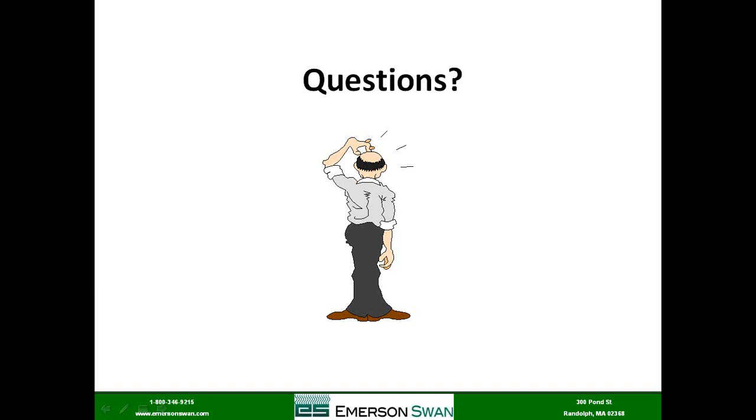George Gray asked a question. With primary secondary piping, is it necessary or advantageous to use all variable speed circulators, or can you just use one for the primary pump? I think either or. I think you could use it for just the primary circulator. It makes a lot of sense there. You could use it for both the primary circulators and your secondary circulators for heat delivery, depending upon what you have out there. I don't think they'll fight each other, but I think that the more you have on that kind of a system, the better it'll perform. But it's not necessarily one or the other. You could put a fixed speed circulator on the primary and use variable speed circulators on your delivery where it's going to do the most good, or you could do both. Again, it's kind of up to you, George.